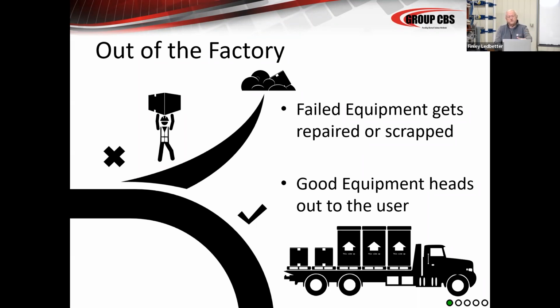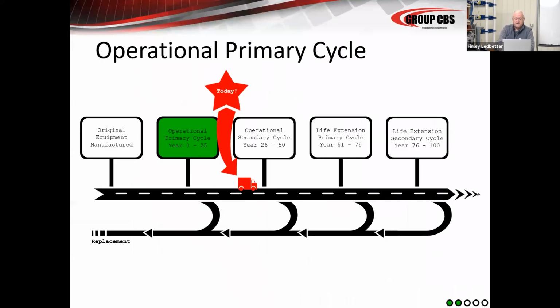Then the good equipment takes the other path and gets sent on this truck and gets sent out to the user. So that's coming toward you. It's coming toward you or your customer, and it's on that truck and it's headed out. There's the switchgear and there's the breakers. It's loaded on the truck and it's headed to you. So now it's through the equipment's original manufacturing process, and we're into your operational primary cycle, which we're going to say is 25 years. We're also going to say that your particular maintenance cycle is every 5 years, that every 5 years, you're going to pull the equipment out of service and do some testing inspection.